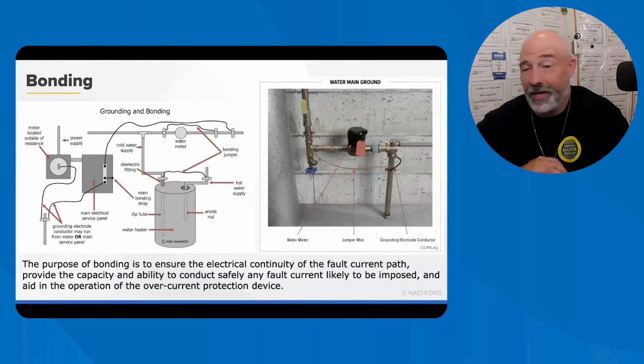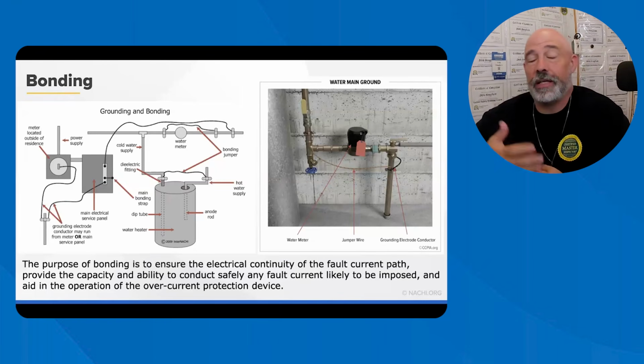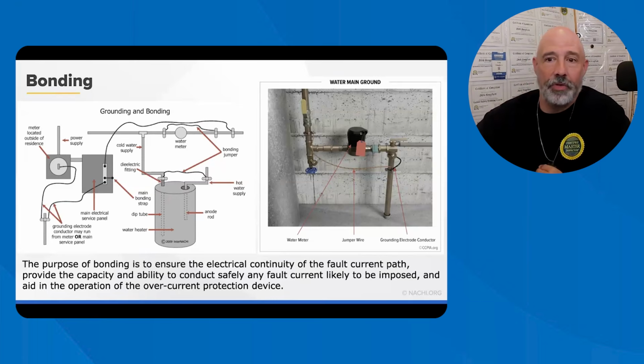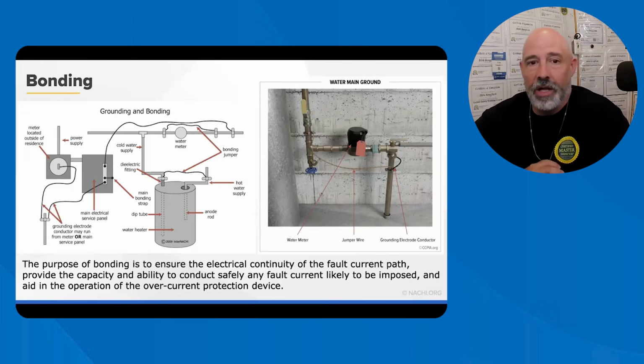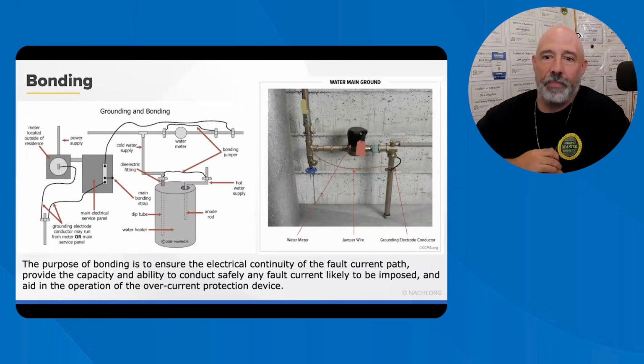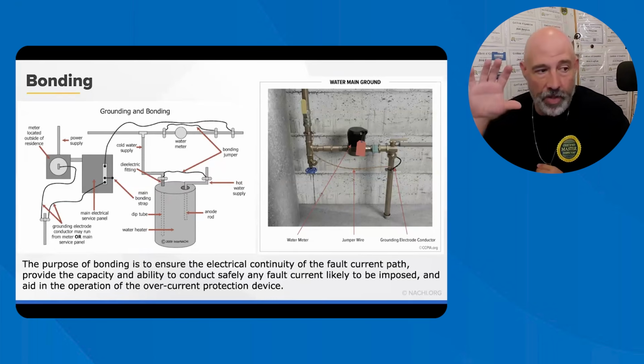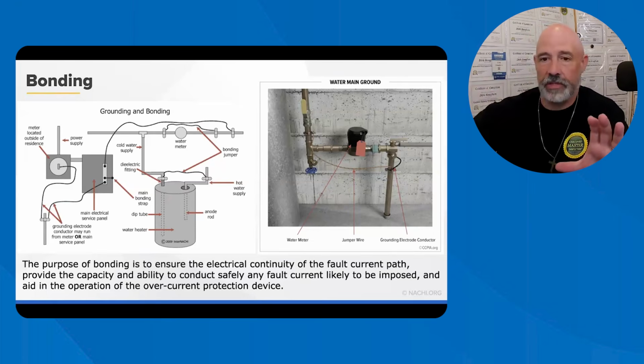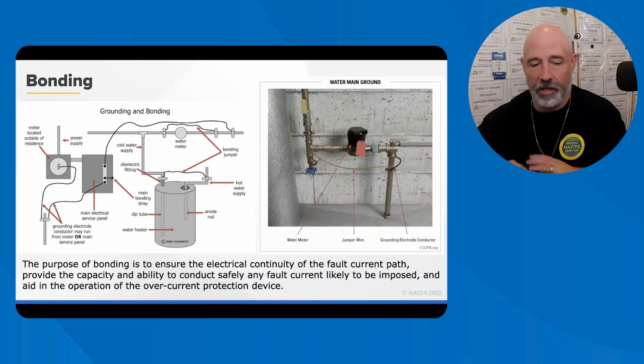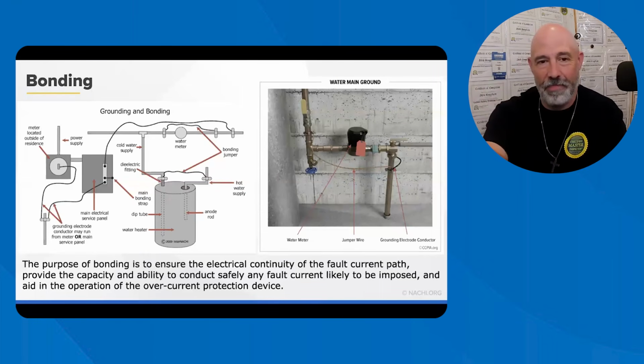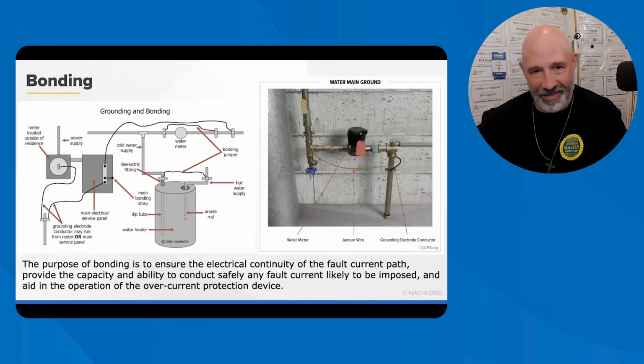The purpose of bonding is simple: to provide a safe path for fault current and help breakers trip more quickly. We've said this before. After the main disconnect, grounds and neutrals must remain separated. So as soon as you look at the main panel, every single panel outside of that should have the neutral and the ground separated. We want to have them married in the main and divorced in everything else.